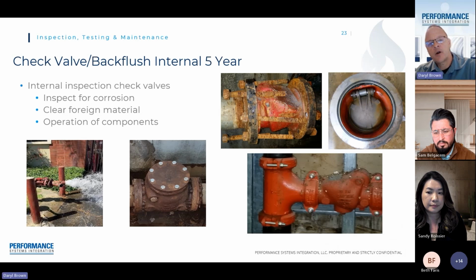These are going back to that fire department connection I showed earlier. You can see there on the left, water actually flowing out of it. So basically, these are utilized, like I said, to pressurize the system by a fire truck if city water pressure goes down. So as you can imagine, if there's any debris in these fire department connections, they actually can push debris into the sprinkler system. So every 5th year, we're required to drain down the system and backflush these to verify they're clear of corrosion. So if the fire department does utilize them, we know they're clean and water will transfer properly into the fire sprinkler system without blockage.